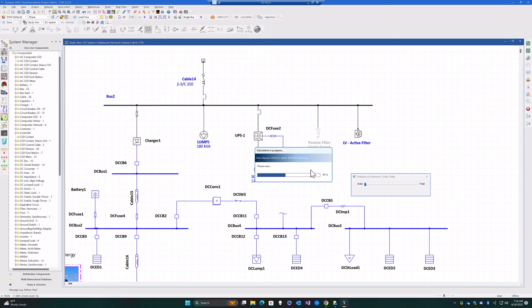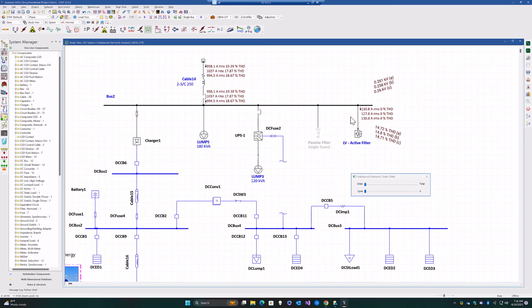And you can see that we are running this analysis as a function of time. And again, what's happening is we are using the proprietary Schneider logic. We are reading the waveforms from the source. We are going through the proprietary logic, and we are trying to inject the harmonics in. So again, in the beginning, as a function of time, the active filter doesn't do anything. There is no injection and no compensation. You can see the distortion is at 19%.